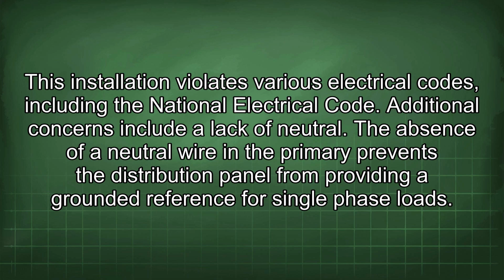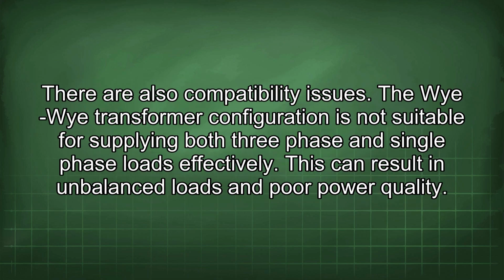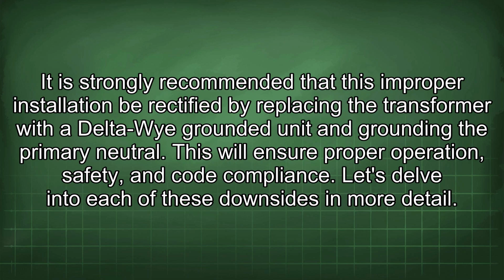Additional concerns include a lack of neutral. The absence of a neutral wire in the primary prevents the distribution panel from providing a grounded reference for single-phase loads. There are also compatibility issues. The Wye-Wye transformer configuration is not suitable for supplying both three-phase and single-phase loads effectively. This can result in unbalanced loads and poor power quality. It is strongly recommended that this improper installation be rectified by replacing the transformer with a Delta-Wye grounded unit and grounding the primary neutral. This will ensure proper operation, safety, and code compliance.